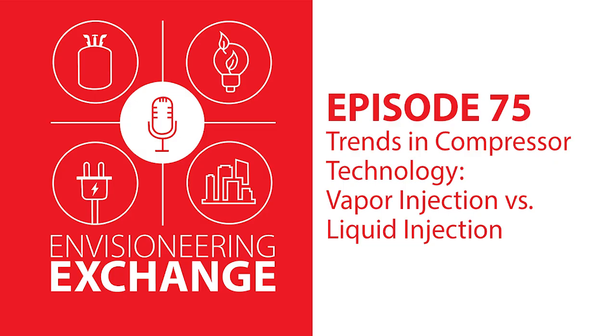Yeah, you can. That's a good point. We've been talking about it just on the heating side, but injection isn't only for really cold climates and low evaporating temperatures. There's still benefit at normal operating conditions and also at higher saturated suction temperatures, even in cooling. A lot of times, if it's a unit that's already designed, maybe they add vapor injection to it and their EER goes up a little bit, or their IEER goes up a little bit. So there are some benefits there.